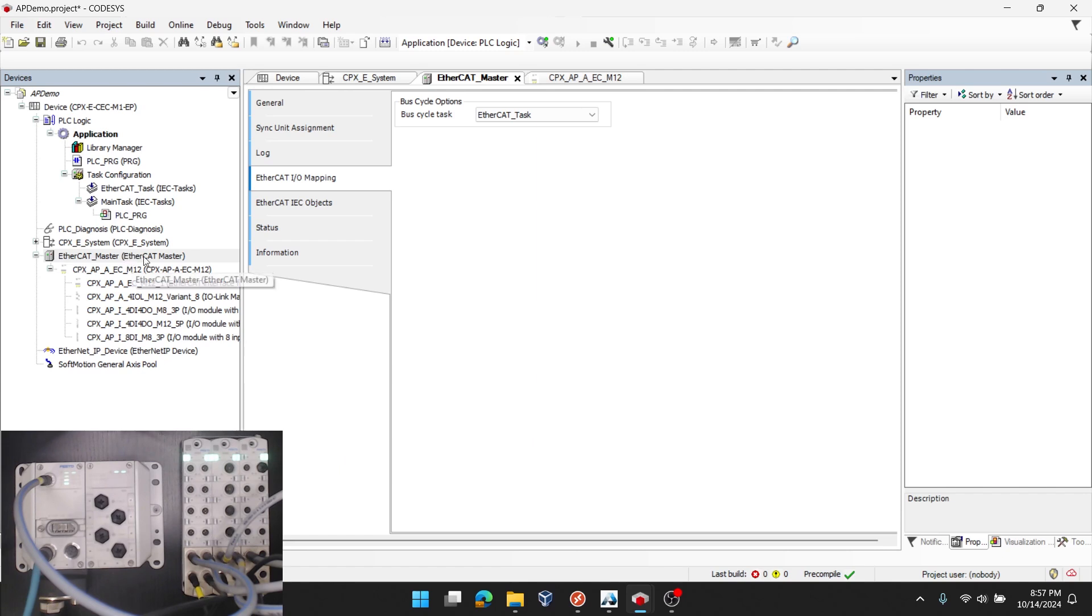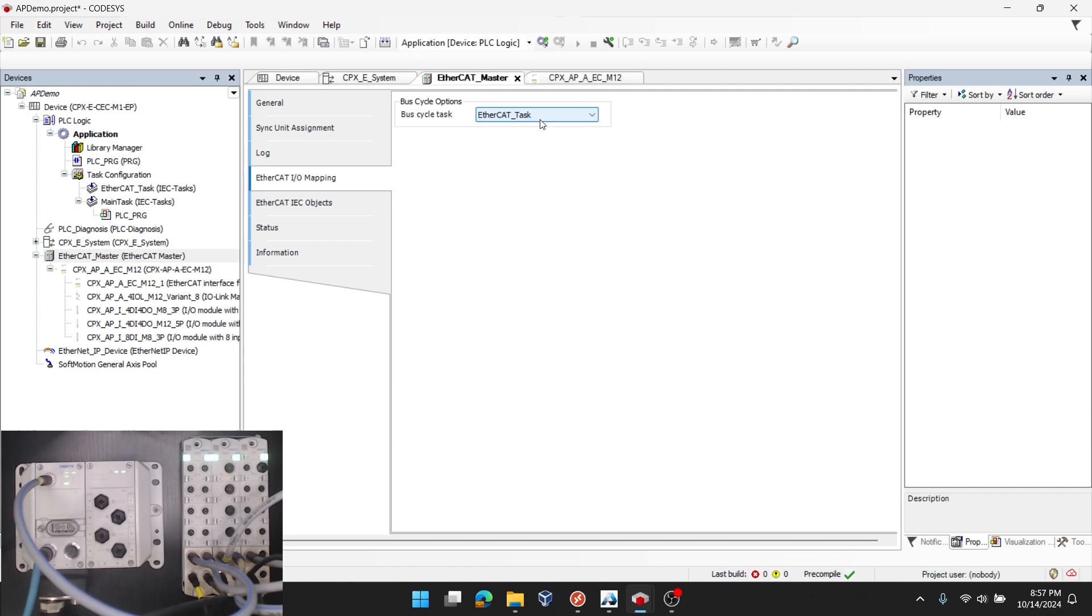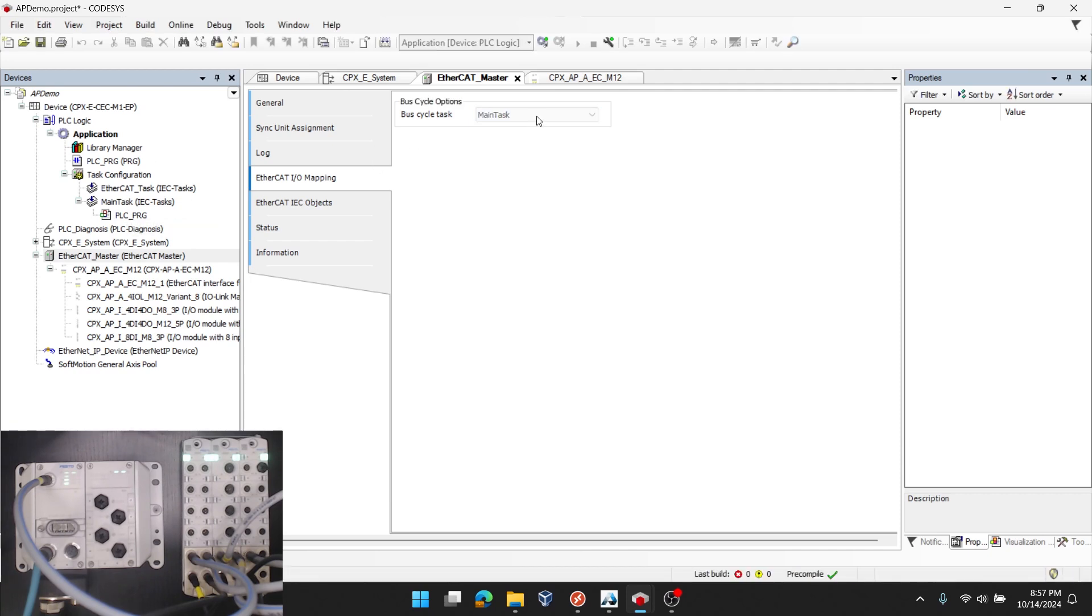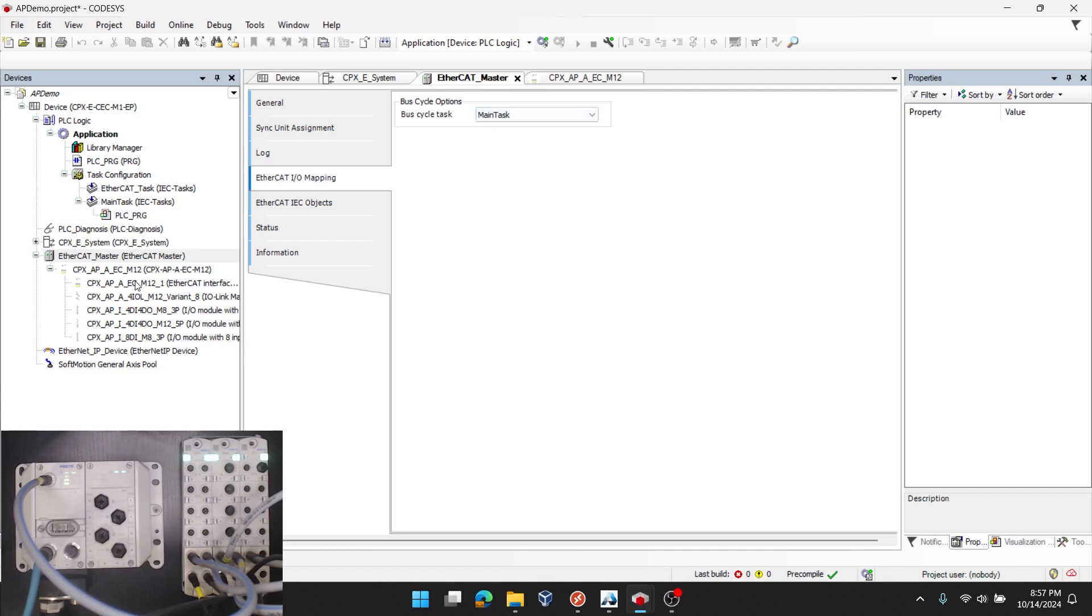Double clicking the EtherCAT master. I want to make sure that everything underneath the EtherCAT master gets updated with the bus cycle. And you can see here that if I expand the EtherCAT master settings, go down to EtherCAT IO mapping, under bus cycle task, I have the default EtherCAT task selected, which as of right now is in my task configuration, but doesn't have anything within it. So I'm going to switch that over to my main task. You could leave it in your EtherCAT task, just refer to another video on task configuration. So I want everything to update with my main task. Great.